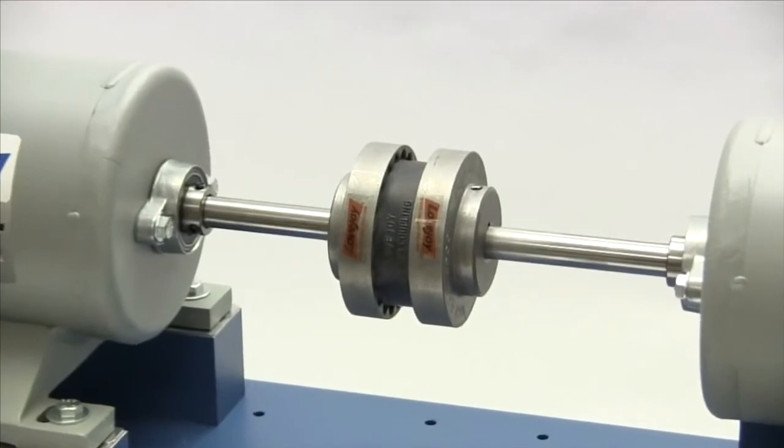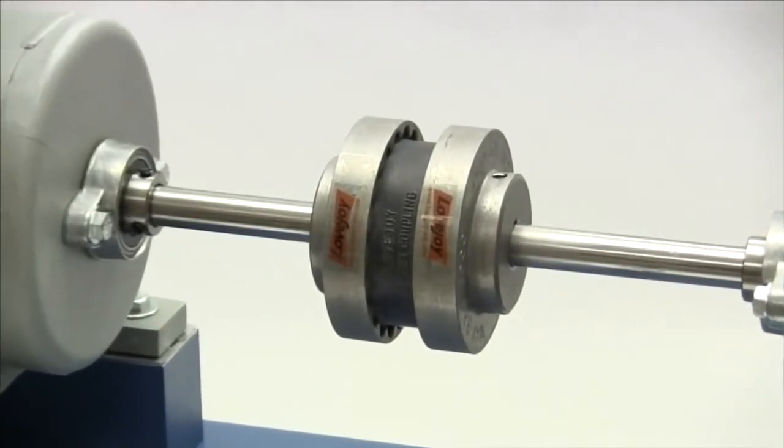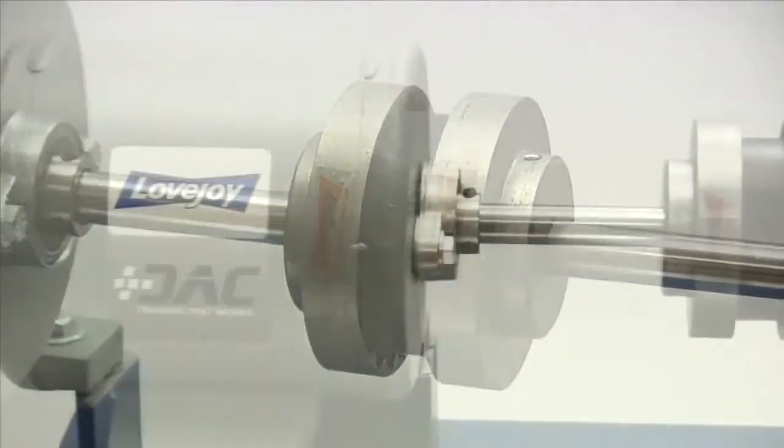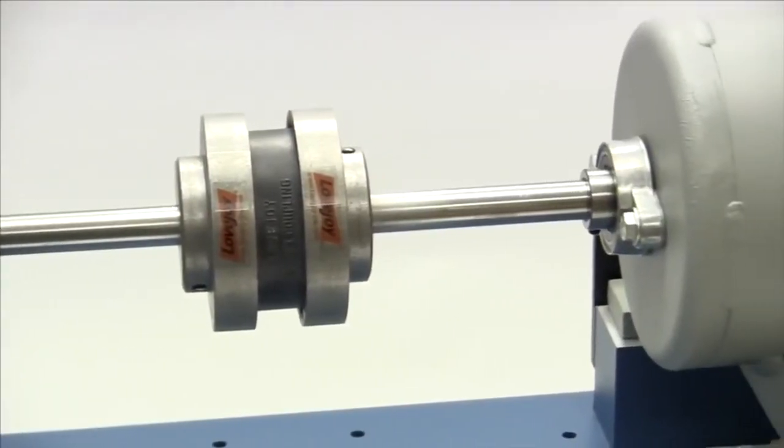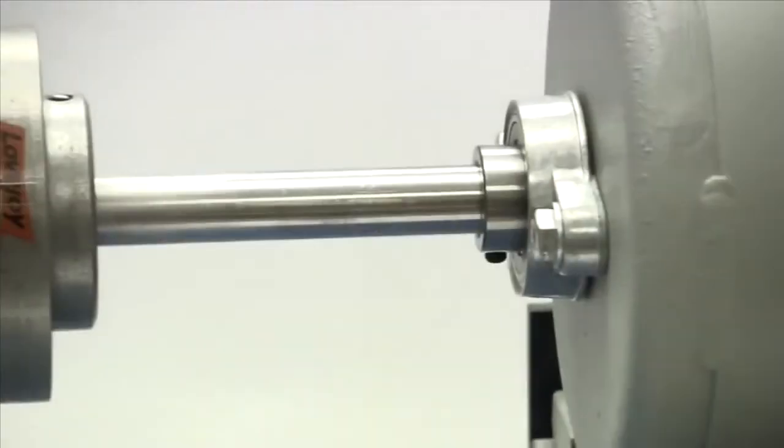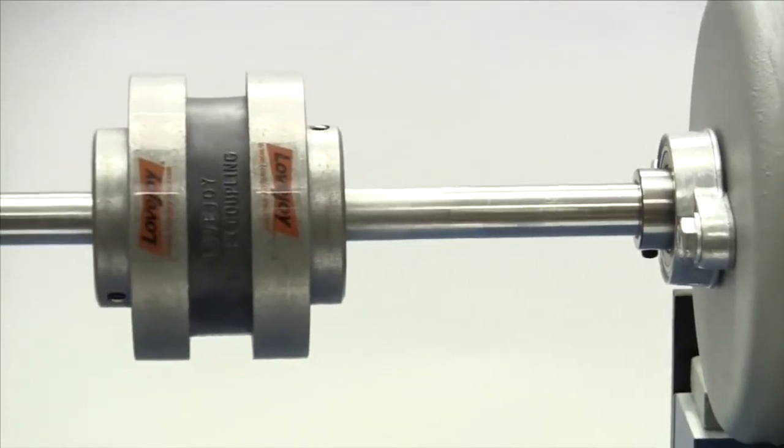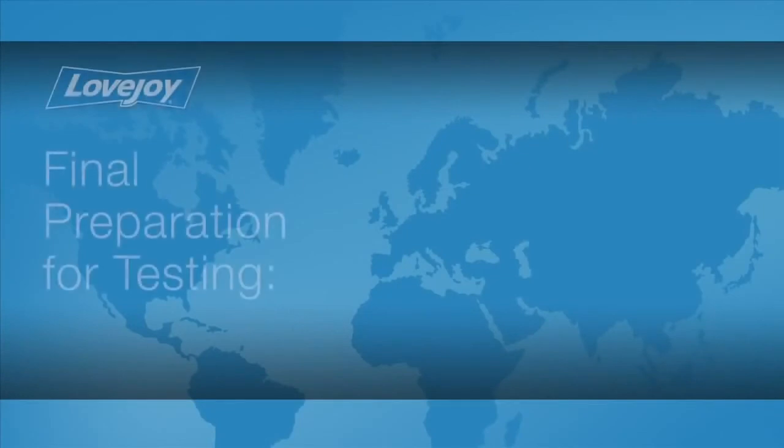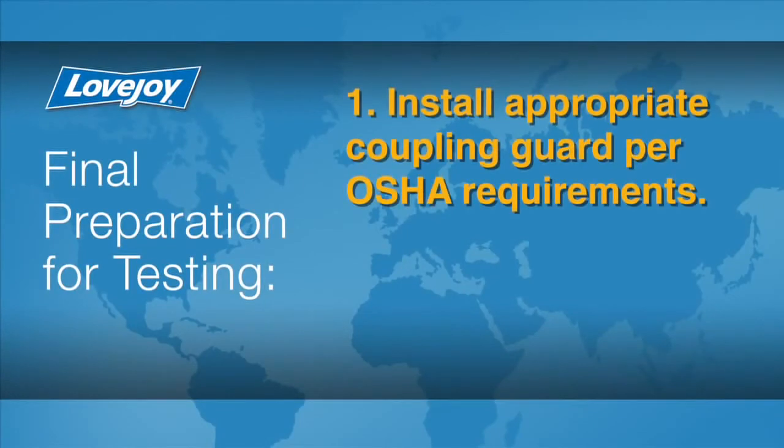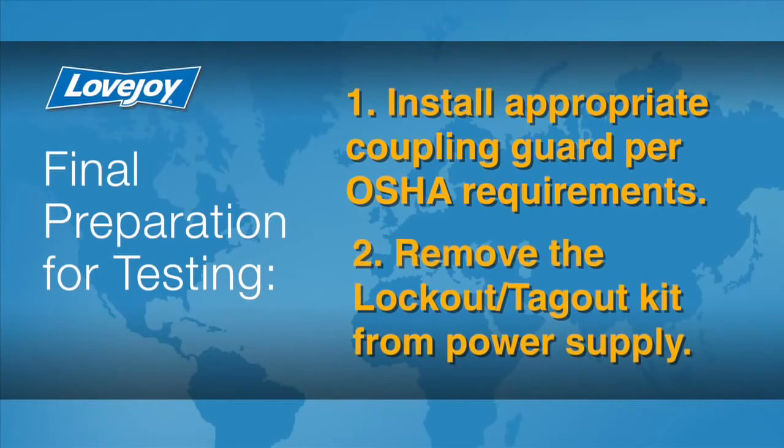When the installation is complete and the equipment is aligned to meet specifications, remove the tooling and material away from the shafting and coupling. Double check the set screw tightness with a calibrated torque wrench, then prepare for testing. Install the appropriate coupling guard per OSHA requirements and remove the lockout tagout kit from the power supply.